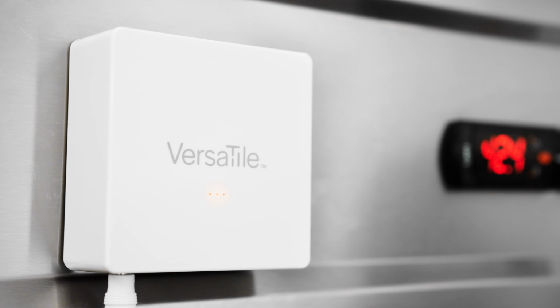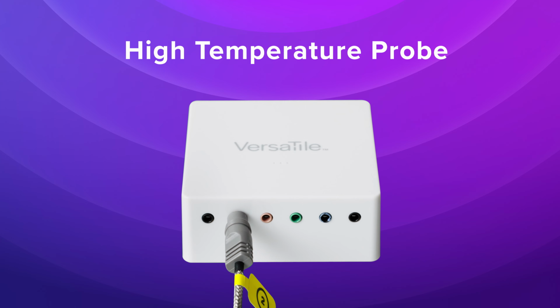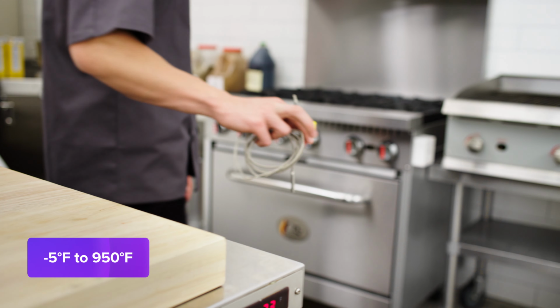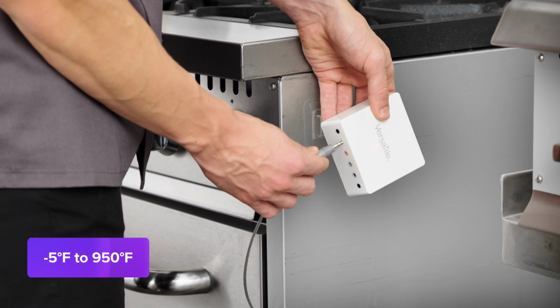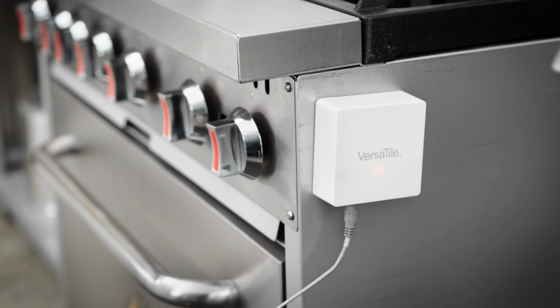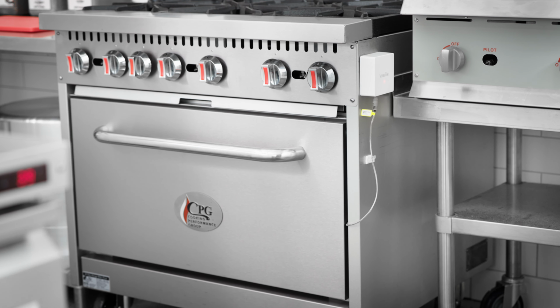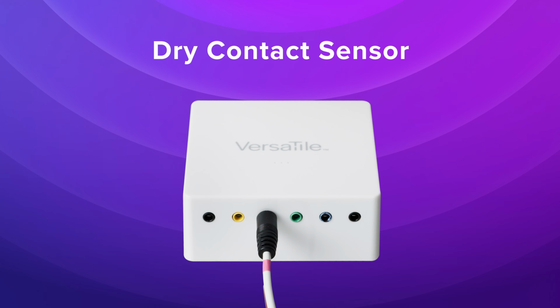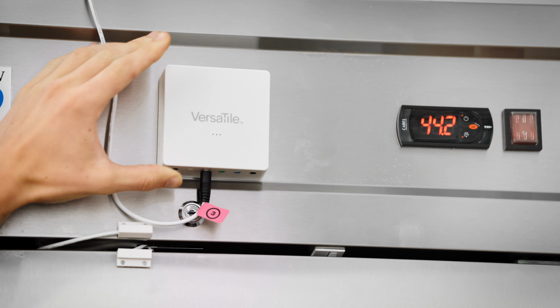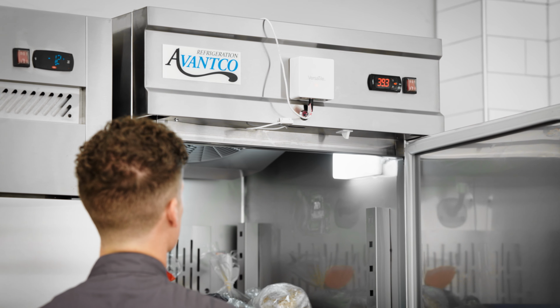general environments. The high temperature probe, -5 degrees Fahrenheit to 950 degrees Fahrenheit range, is useful for monitoring cooking equipment and other high heat locations. The dry contact sensor is useful for monitoring something that can open and close, like the doors of any equipment or doors to an establishment.